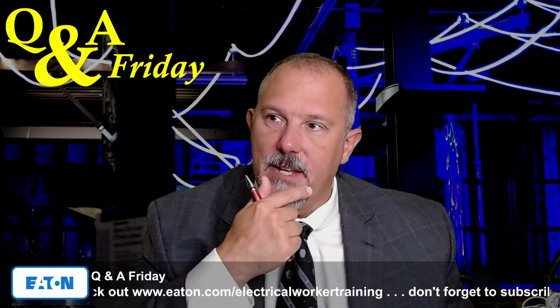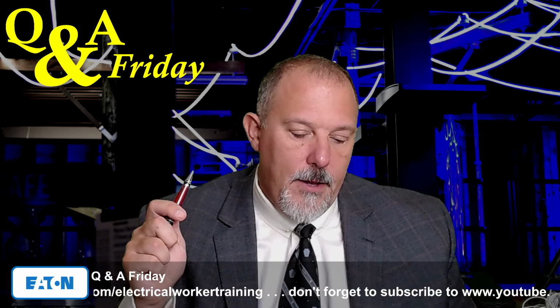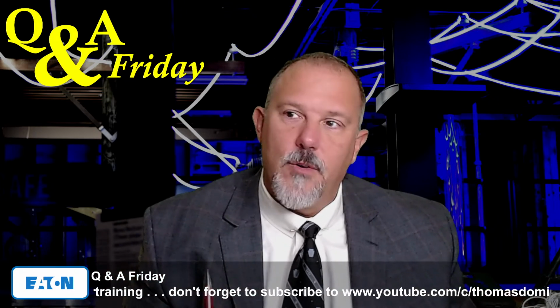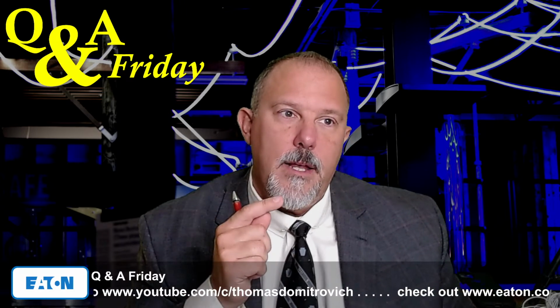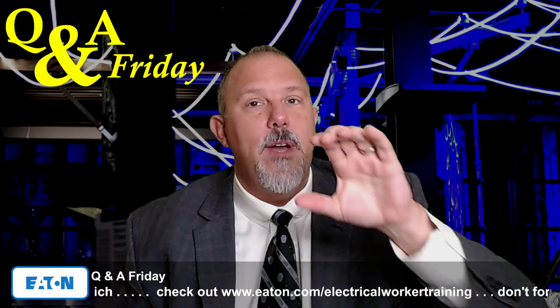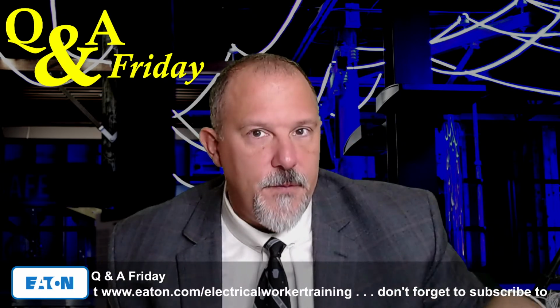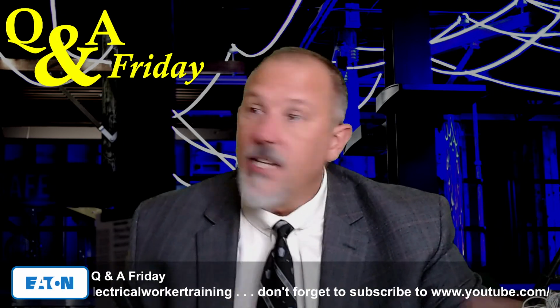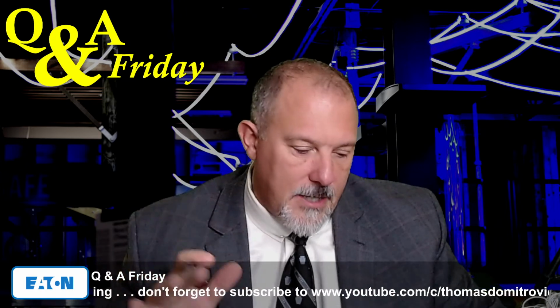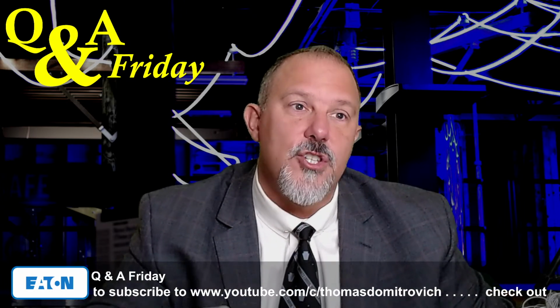I can remember talking to John McCamish about this, and the reason was not for what we stated in that video. It was because the moment you land a conductor on the secondary of that breaker, it could be a service overcurrent protected device, but it's also protecting the feeder. So you have to follow the rules of the feeder protection, which puts you into 215. And obviously it's a service overcurrent protected device, which puts you into 230. So I think that this discussion is a good example that an overcurrent device can serve two functions and have to meet two different areas of the National Electrical Code. So be mindful of that. That was a very good observation, and I wish I had the entire context for you.